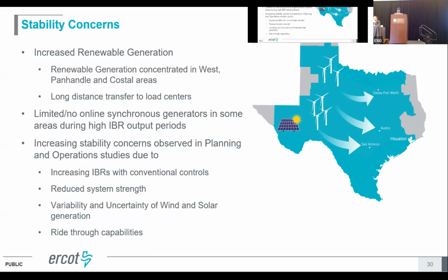So that's where the main challenge comes in. With increased renewable penetration, we're now at a point where ERCOT has small pockets or small interfaces where we've been seeing stability concerns because of too much concentration of renewable generation, without much transmission capacity to bring it to the load pockets, and also not enough voltage support. So we are adding units, but not adding shunts, SVCs, or any dynamic reactive devices to maintain the voltage in those heavily concentrated IBR areas.